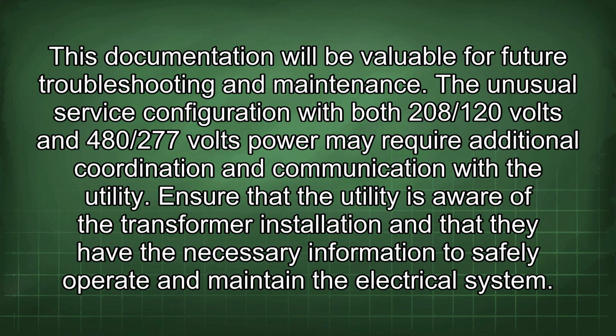The unusual service configuration with both 208/120 volts and 480/277 volts power may require additional coordination and communication with the utility. Ensure that the utility is aware of the transformer installation and that they have the necessary information to safely operate and maintain the electrical system.